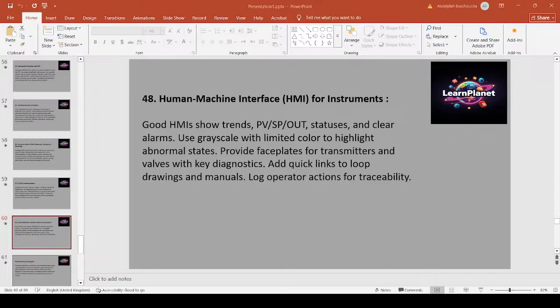HMI should present PV, SP, output, diagnostics, and trends clearly with limited color use for abnormal states. Use faceplates for each instrument so operators can quickly access diagnostics, set points, and maintenance history. Provide quick links to loop drawings and standard operating procedures, and log operator actions for accountability. Design HMI with role-based access control so only trained personnel change control parameters. Example: create a valve faceplate showing position, travel time, last maintenance, and ability to force in maintenance mode with audit trail.